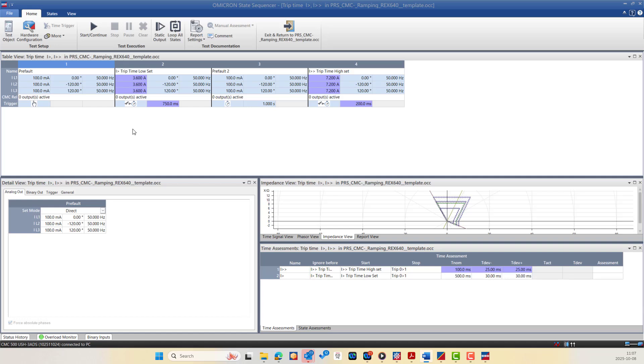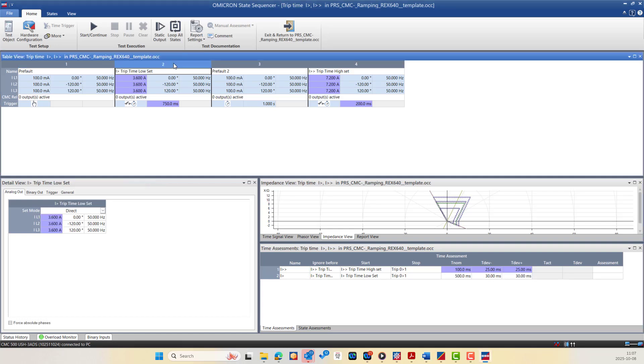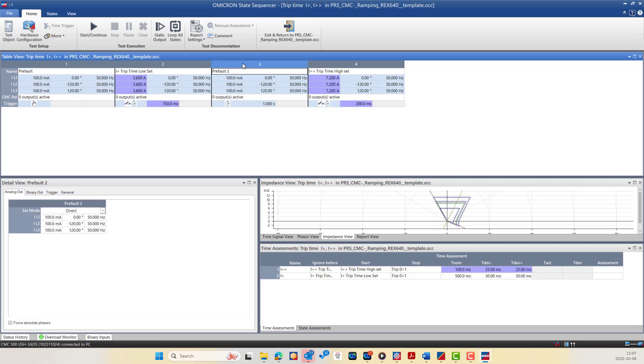This versatility makes the test sequence ideal for testing realistic protection functions such as trip time for stages like I-greater and I-double-greater over current protection, switch-onto-fault, auto-reclose, and circuit breaker fail protection. The module is structured to let you define and organize a series of test states that the CMC outputs sequentially. You can rename each state with a meaningful name, such as 'Pre-fault' for state one, 'I-greater Trip Time' for state two, 'Pre-fault' again for state three, and 'I-double-greater Trip Time' for state four.